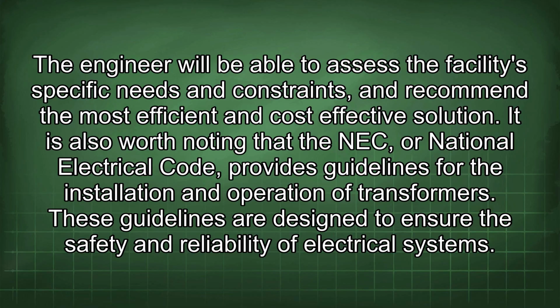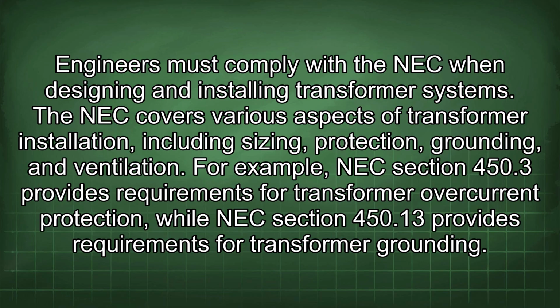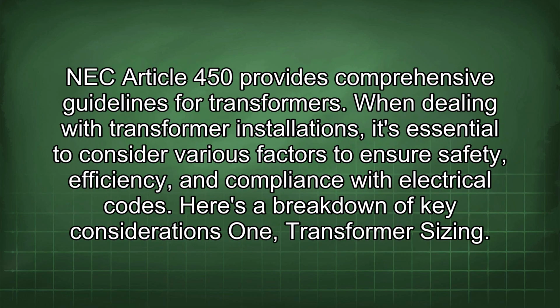solution. It is also worth noting that the NEC, or National Electrical Code, provides guidelines for the installation and operation of transformers. These guidelines are designed to ensure the safety and reliability of electrical systems. Engineers must comply with the NEC when designing and installing transformer systems. The NEC covers various aspects of transformer installation, including sizing, protection, grounding, and ventilation. For example, NEC Section 450.3 provides requirements for transformer overcurrent protection, while NEC Section 450.13 provides requirements for transformer grounding. NEC Article 450 provides comprehensive guidelines for transformers.